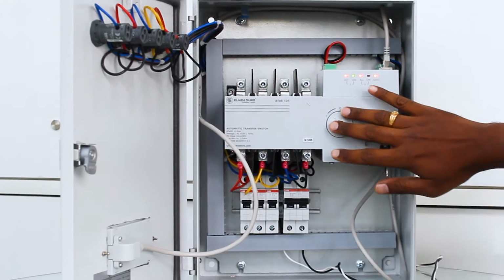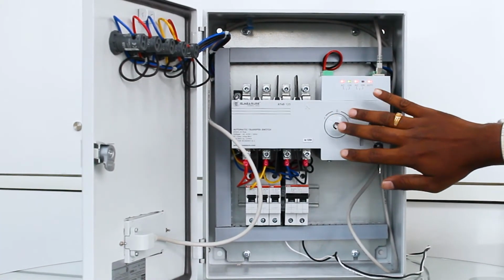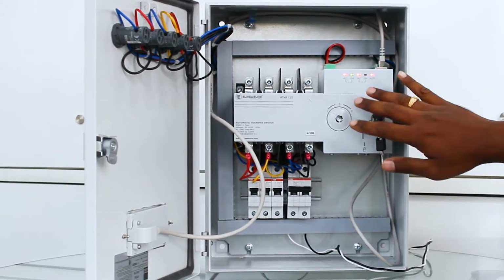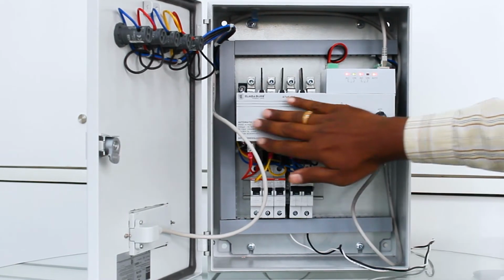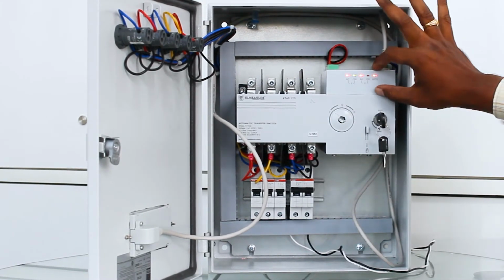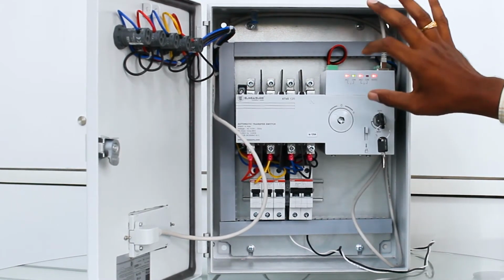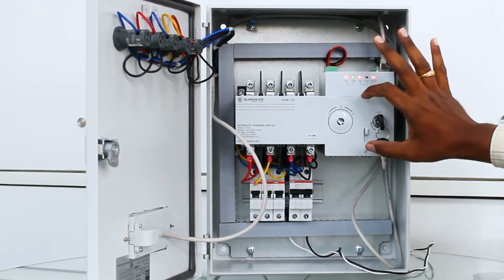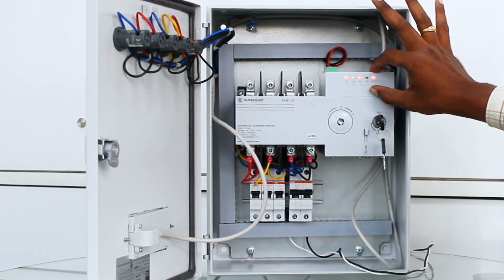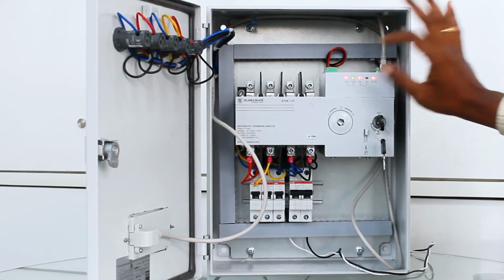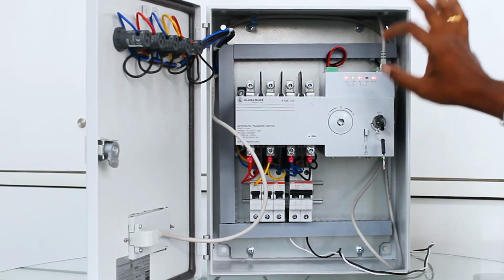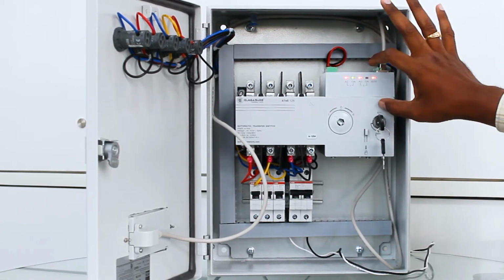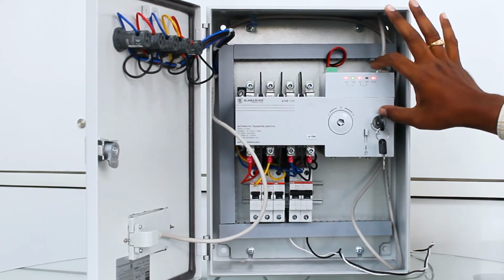So this is the device, a 125 amp motorized changeover. Here we have segregated the 2 parts: this is the mechanical part and this is the electronic part. In the main features of the Elmeasure ATS, we have an ATS with an inbuilt microprocessor-based intelligent controller. In this controller, we have all electrical protections at incomer level, like voltage, frequency and phase sequence protection.